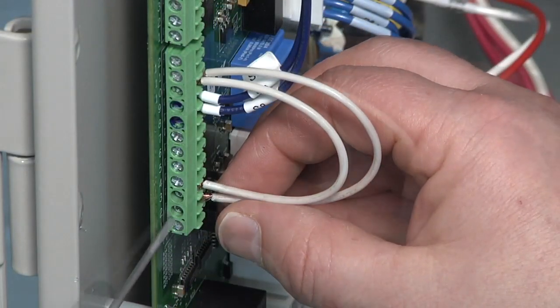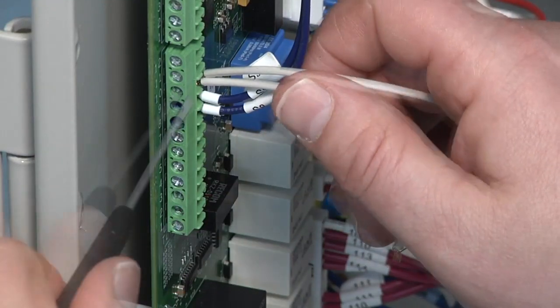Don't forget to remove the jumpers from the drive and bypass before returning the system to normal operation. Once the jumpers have been removed, you're done. The bypass has been successfully set up and is ready for safety circuits to be attached in place of the jumpers we just removed.